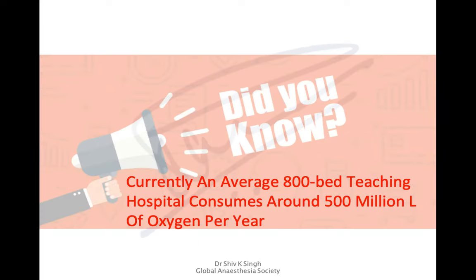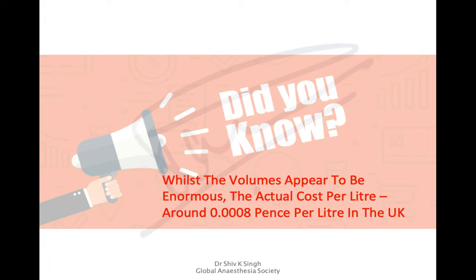An average 800-bed teaching hospital consumes around 500 million liters of oxygen per year. Using a VIE, the cost per liter is around 0.0008 pence per liter in the UK — making oxygen relatively inexpensive despite the large volumes consumed.